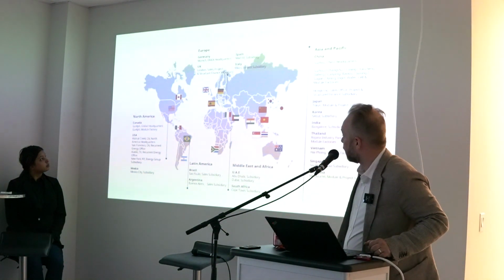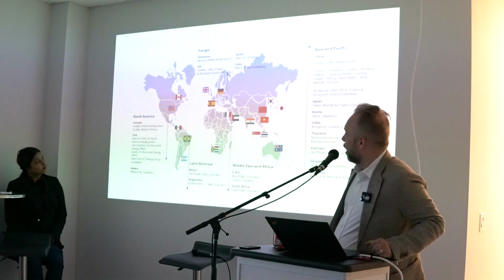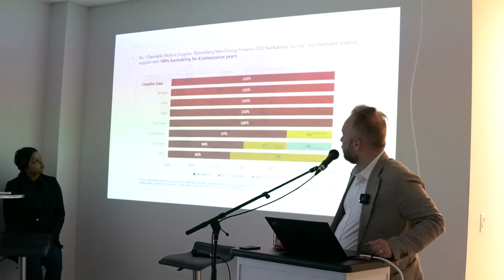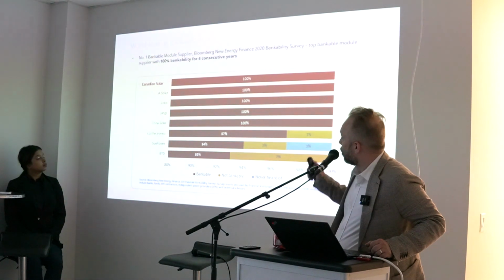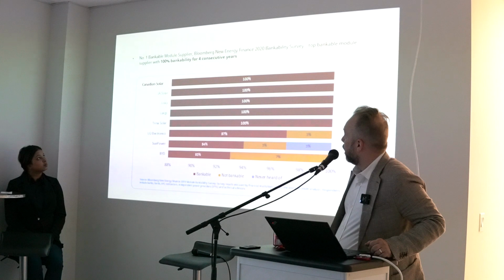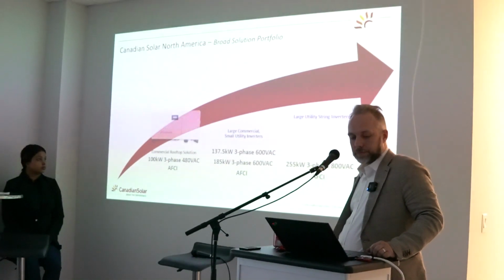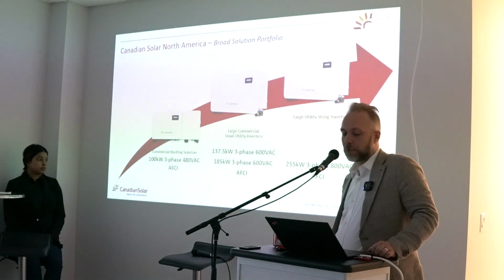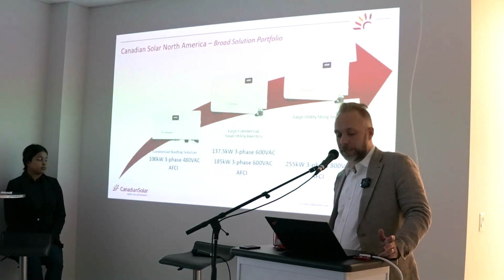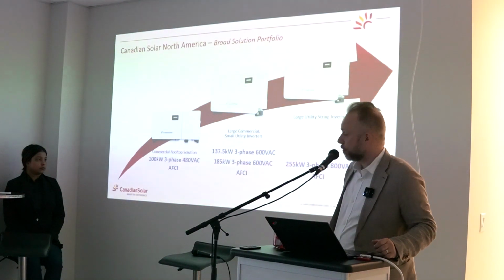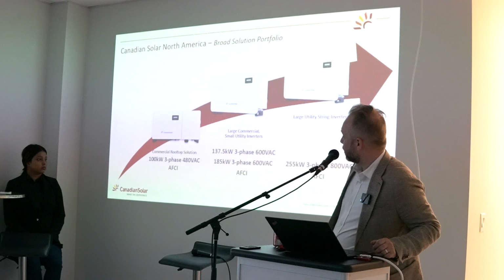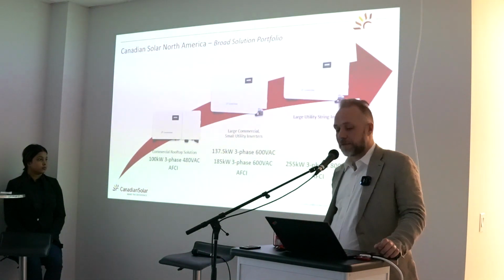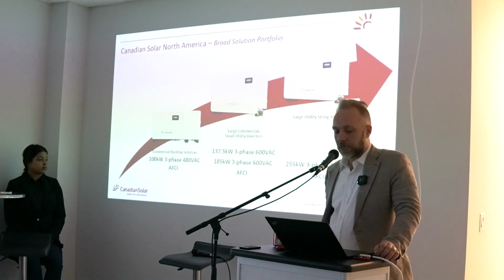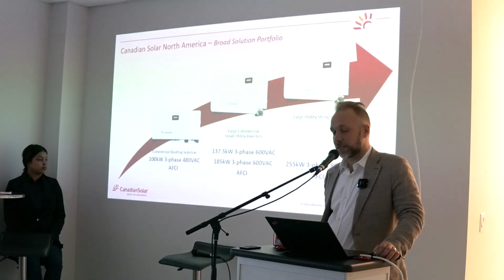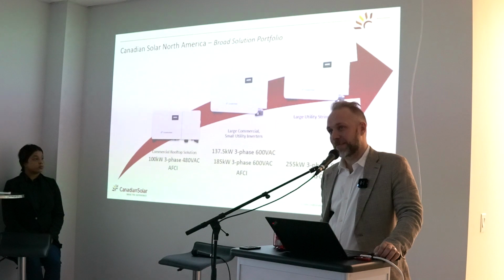As you can see, that goes back to the Canadian Solar presence. That's not our presence, unfortunately. All over the world, they have local offices. As far as bankability, again, on the Bloomberg list, over 100% approval rating there for 4 consecutive years. And then the products that we'll talk about today, there's 3 products that we carry from Canadian Solar on the inverter side. There's a 100 kilowatt 3-phase 480 volt inverter. And then the product that we sell most of is the 137.5 kilowatt and 185 kilowatt 600 volt AC inverter. And then also another product we're selling more for utility size stuff is the 255 kilowatt inverter that is 800 volt AC. That's more a product focused on 10 megawatts plus.